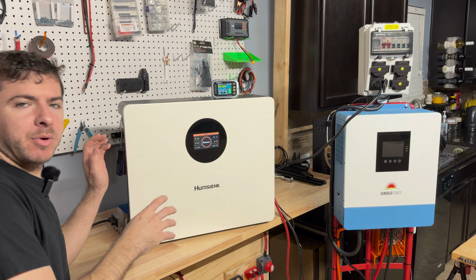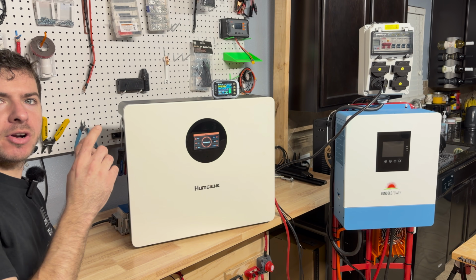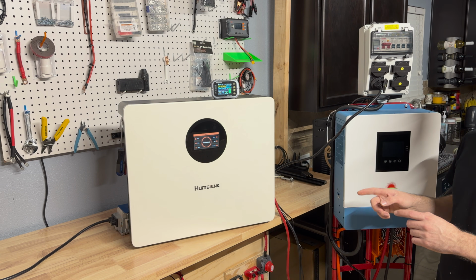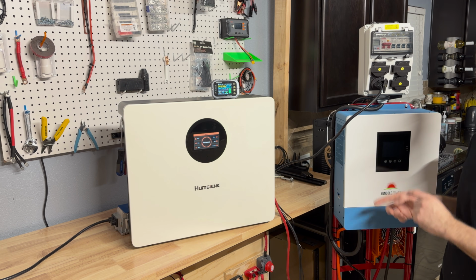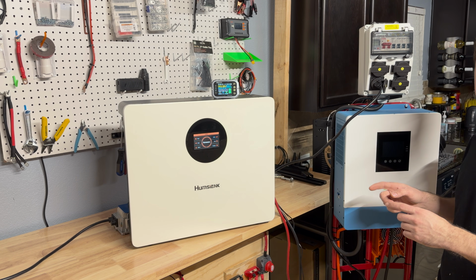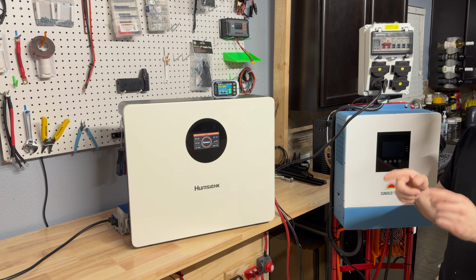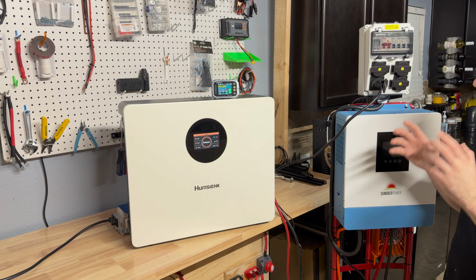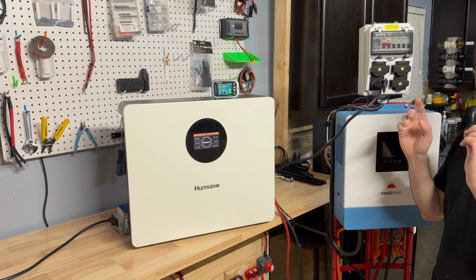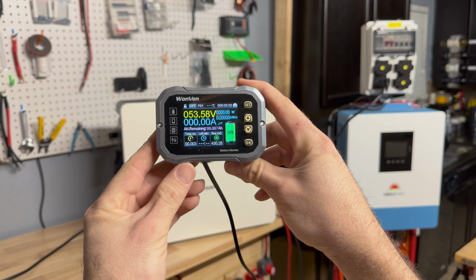I went ahead and got the battery completely fully charged. Now we're going to go ahead and run our capacity test. We're going to put a 0.2C load on the battery, so we're going to run about 20 amps on the DC side. I'm going to use a battery charger connected to our 48 volt off-grid solar power system to supply the load. Once the battery is completely discharged, we're going to be able to see the final result on our little current shunt.